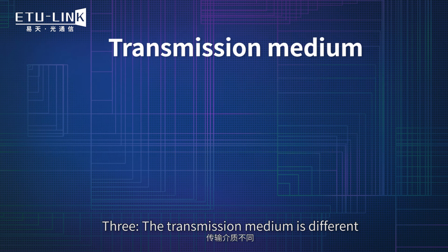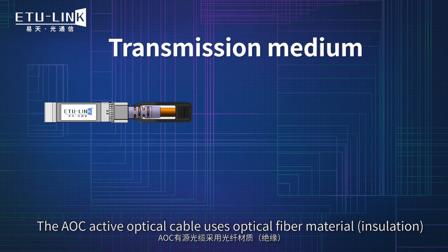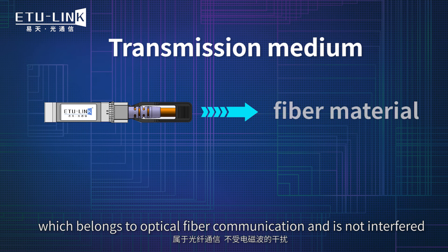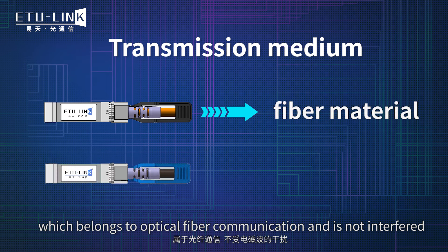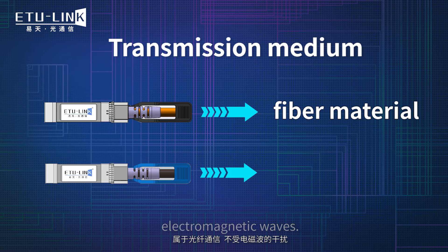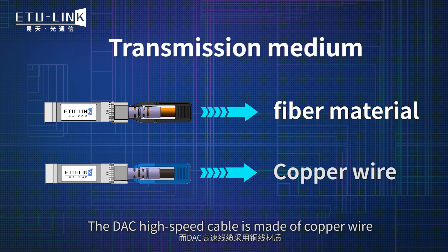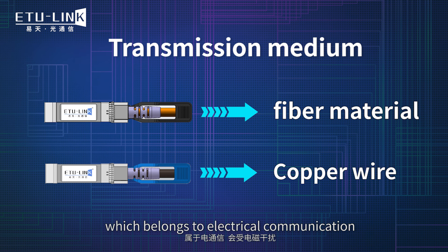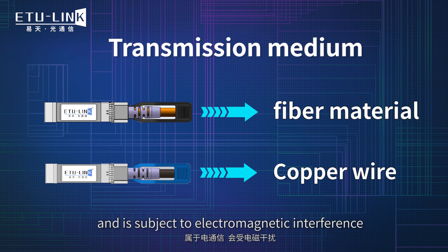Three: the transmission medium is different. The AOC active optical cable uses optical fiber material, which belongs to optical fiber communication and is not interfered by electromagnetic waves. The DAC high-speed cable is made of copper wire, which belongs to electrical communication and is subject to electromagnetic interference.